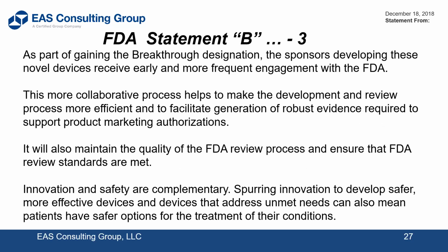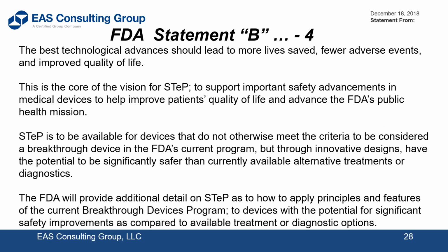This is just their statement of goals that actually started driving the breakthrough program and the STEP program. So we won't spend a lot of time on this. Just be aware of this if you have a chance to go back over it. If you're actually contemplating these programs, it'll give you an idea of the areas where they want STEP to work and where they want breakthrough devices to work. So if you have a device that falls in any of those areas, you certainly want to look at the opportunities available by taking advantage of one of those programs, and then approaching the agency through what's called a Q-Submission program, which has a guidance document that explains that program as well.